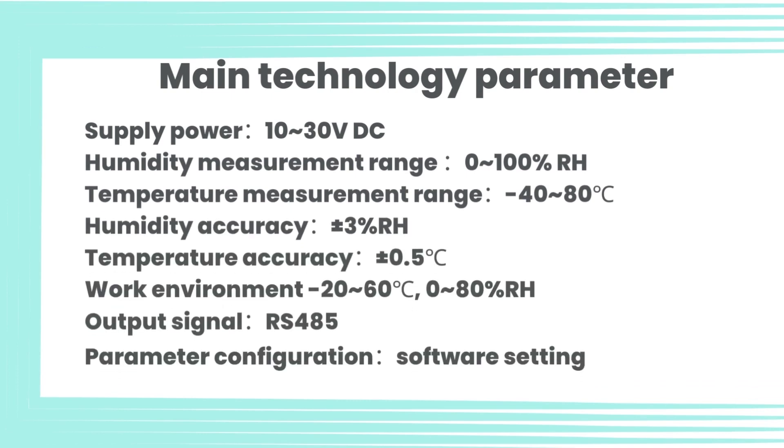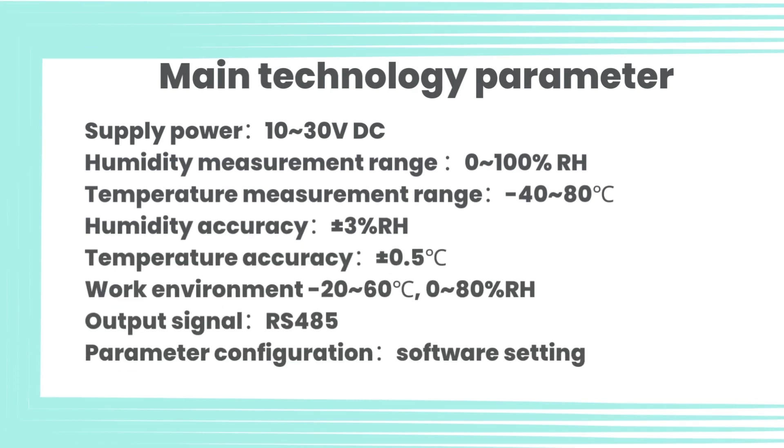Main technology parameters: Supply power 10-30V DC, humidity measurement range 0-100% RH, temperature measurement range -40 to 80 degrees Celsius, humidity accuracy plus or minus 3% RH.